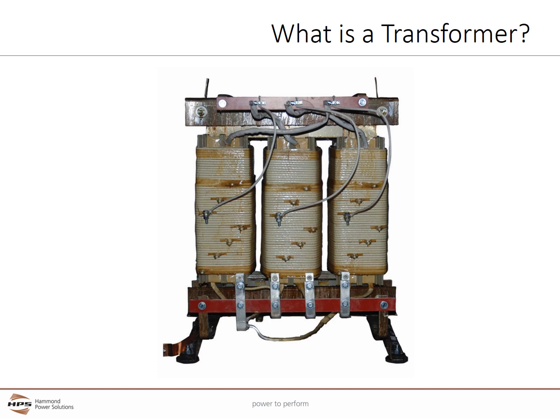This is a typical three-phase drive isolation transformer. With 3 sets of lugs and wires on the top and 4 sets of lugs and wires on the bottom of the unit, this is wired in a delta Y configuration with a neutral in the secondary. A line reactor does not have a neutral. Another major visual difference is the presence of voltage taps on the coils. By adjusting the taps, the user can fine-tune the voltage up or down in 1 to 4 increments, with each increment typically being 2.5% or 5%.